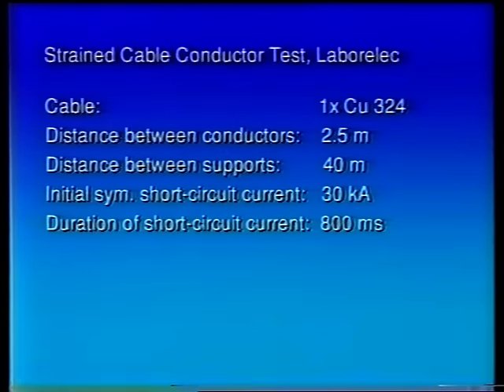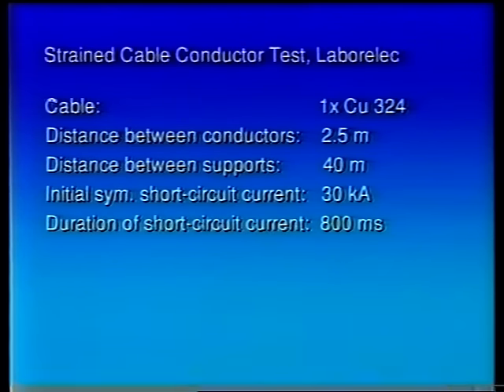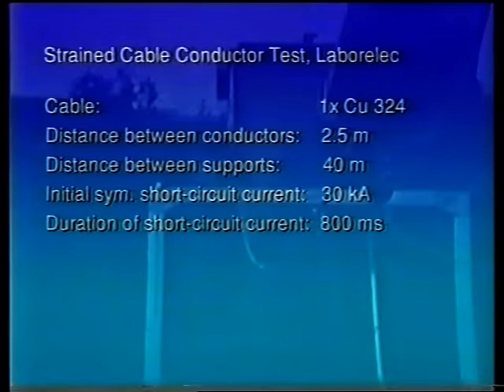Another 40-metre span is shown in the next test. Here, the influence of feeding droppers is included. It's an important fact that portals are not as rigid as usually assumed, and that their mechanical behaviour influences the tensile forces in the cables a lot.